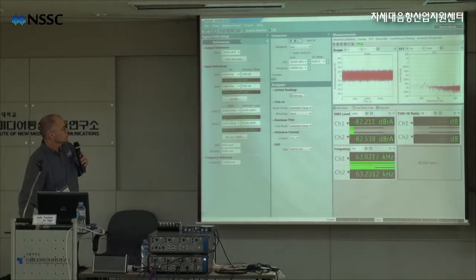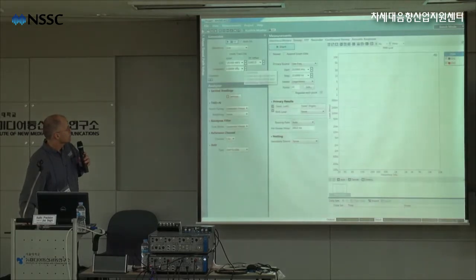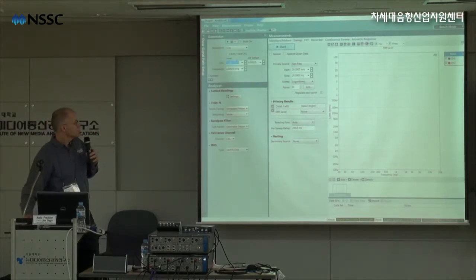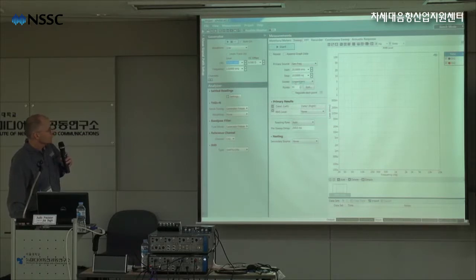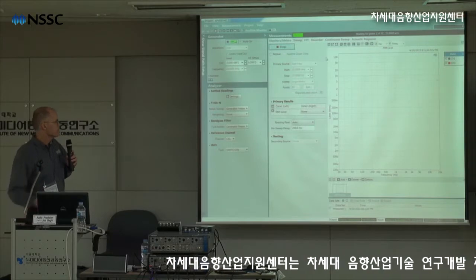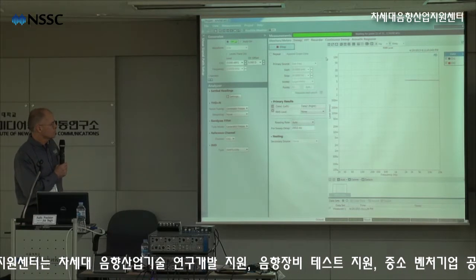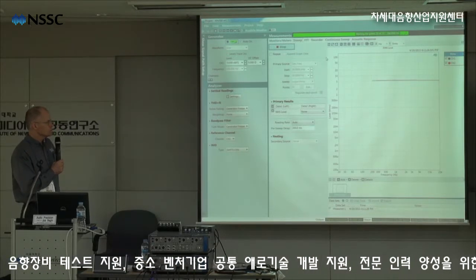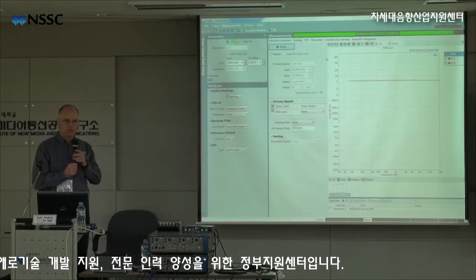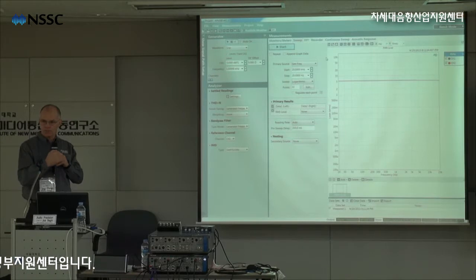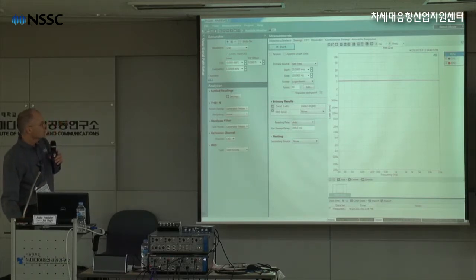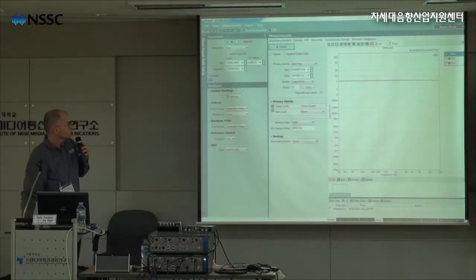So one way to do this would be with a conventional sweep. Let's try 0 dBFS. So we have a 31-point sweep from 20 to 20K. The analyzer, by default, sweeps from high frequency to low frequency. The reason for that is the signals settle very quickly at high frequency, and it takes longer to settle at low frequency. So you can see here the RMS level. We did a stepped sine measurement here.